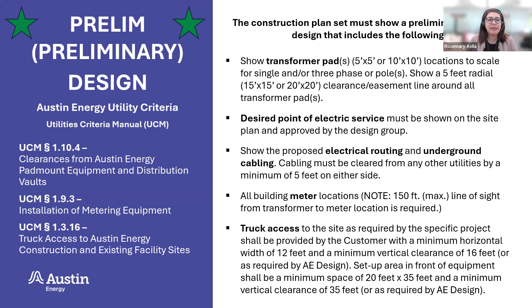Thank you, Rosemary. One of the main things that we review for proposed development, especially new buildings, anything above grade and below grade, are clearances. This is all outlined in our criteria manual. UCM 1.10.4 talks about clearances. And for overhead distribution lines, permanent structures have to maintain clearances that are required in the National Electric Safety Code, as well as the Austin Energy Design Criteria Manual. And as we saw earlier, maintain OSHA clearances for safe working conditions. Nothing can be installed over or under our overhead distribution facilities.